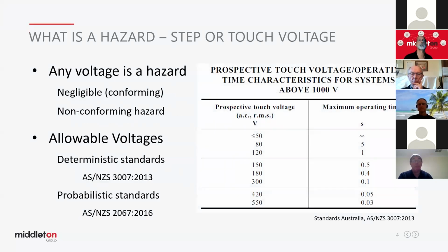So what's a hazard? We're looking specifically at step and touch voltages. There are lots of hazards around, but let's concentrate on the electrical ones. Really, any voltage is a hazard. There's no such thing as no hazard. So we look at any voltage that may appear on a conductive surface during an earth fault as hazardous. But what's negligible, which is conforming, and what might be a non-conforming hazard?